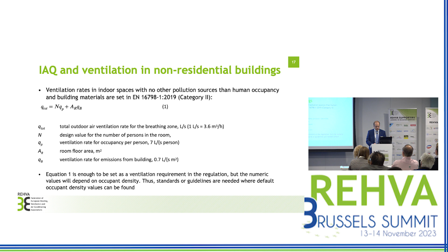And as there can be natural ventilation systems, hybrid ventilation systems, then an alternative approach is to determine the ventilation airflow rate from the CO2 concentration. This is also important. So it is possible to calculate limit values for the CO2, and if the rooms are equipped with CO2 sensors, then ventilation can be controlled based on these CO2 readings.